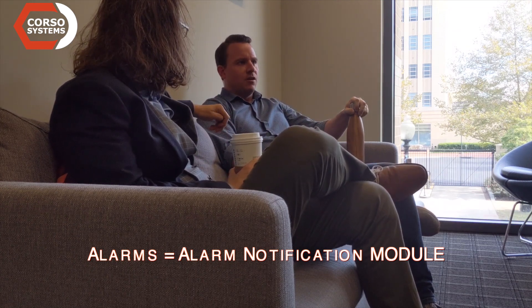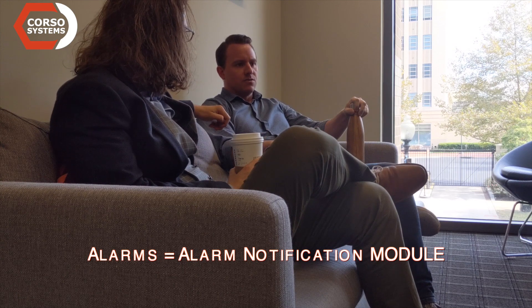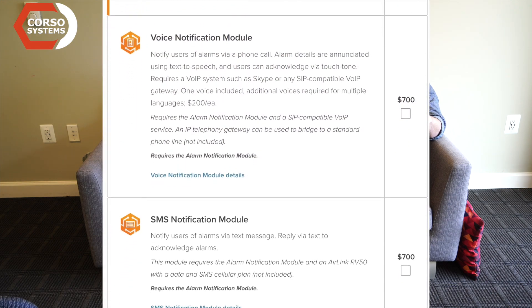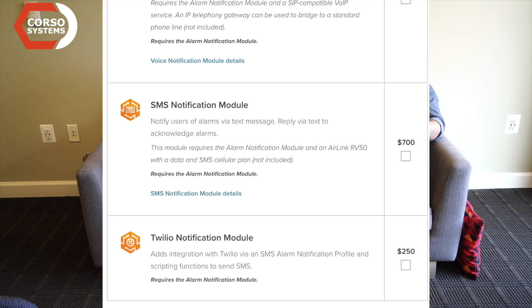Alarm notification allows you to send out email alerts on alarm conditions. The other modules beyond that allow you to do SMS text messages, integrate with Twilio for phone calls or SMS, or use the voice notification module — which is text-to-speech — that will basically call you and read you the alarm in a computerized voice. You can acknowledge alarms via phone, via email, or via SMS. They also allow you to set up alarm rosters and notification pipelines.